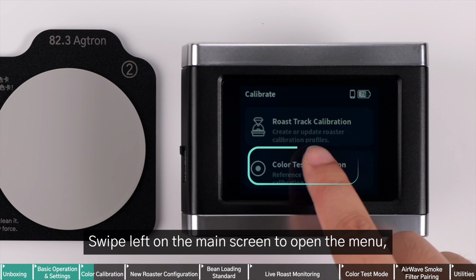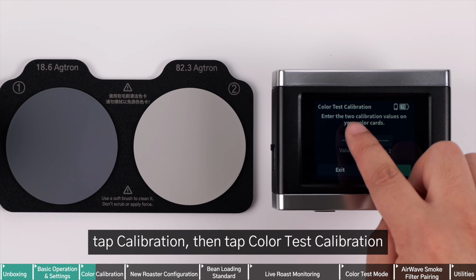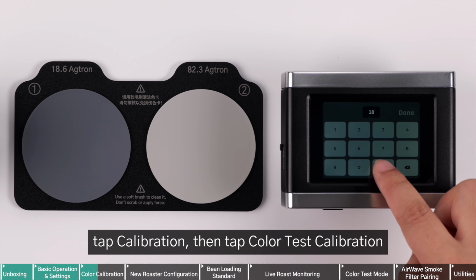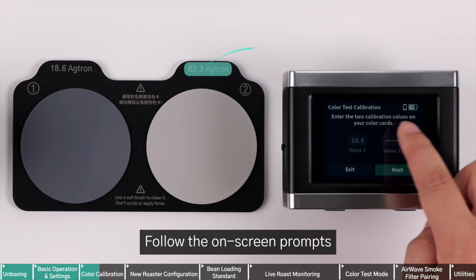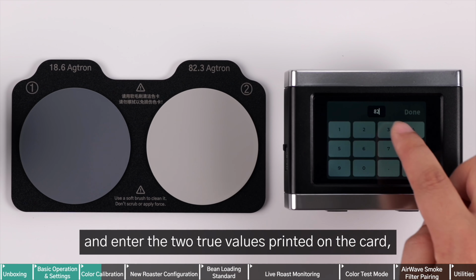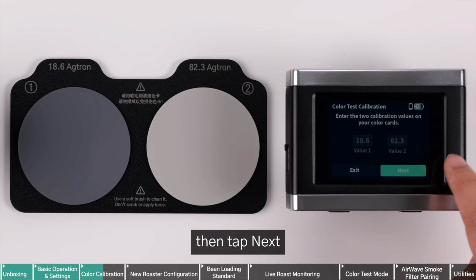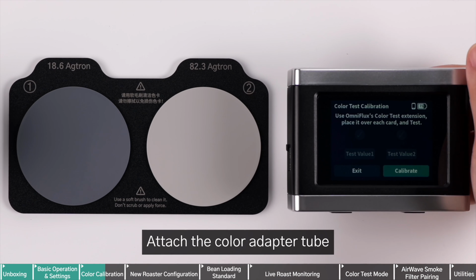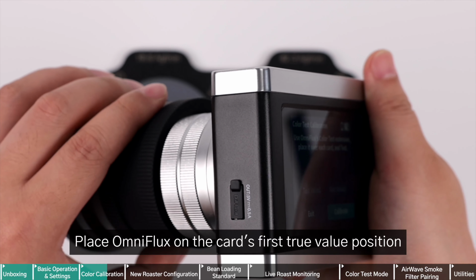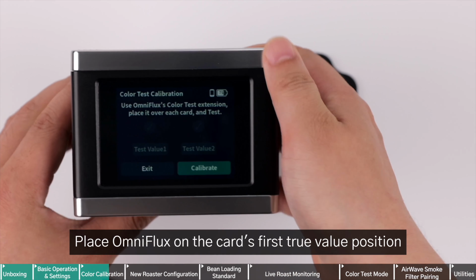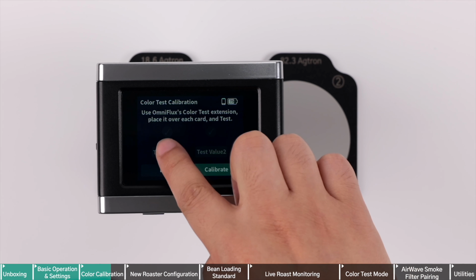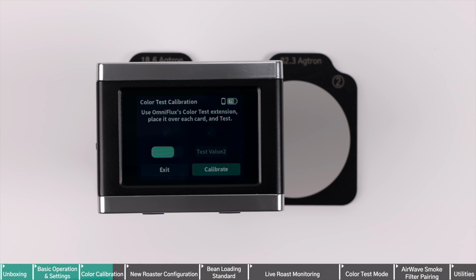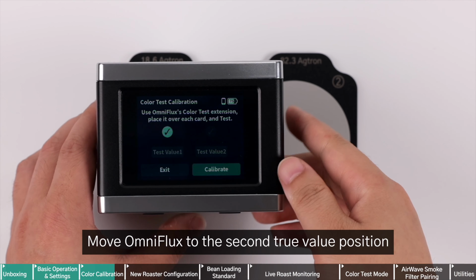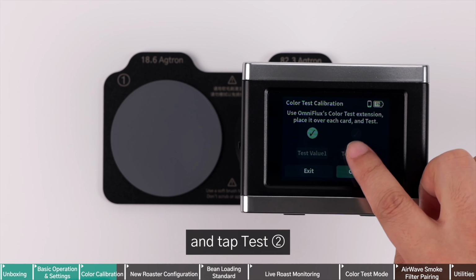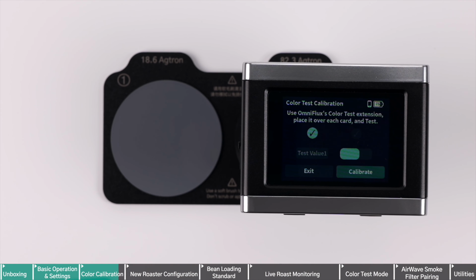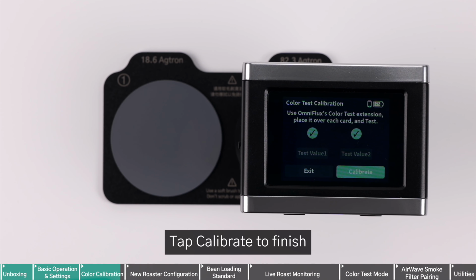Swipe left on the main screen to open the menu. Tap Calibration, then tap Color Test Calibration. Follow the on-screen prompts and enter the 2 true values printed on the card, then tap Next. Attach the color adapter tube. Place OmniFlux on the card's first true value position and tap Test 1. Move OmniFlux to the second true value position and tap Test 2. Tap Calibrate to finish.